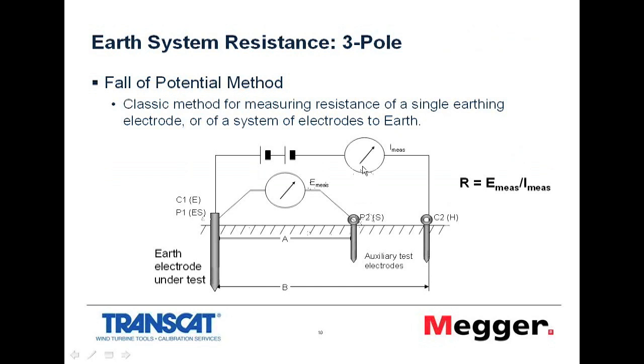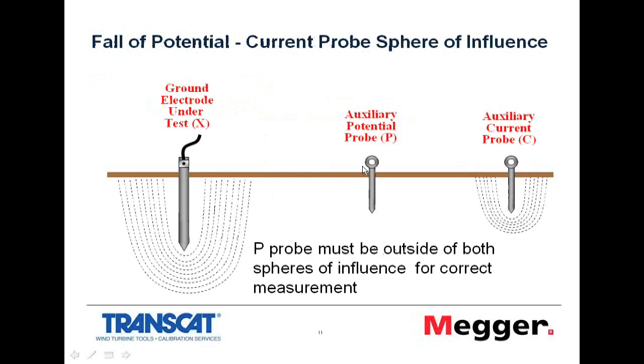Okay. However, we also have to take into account that the ground electrode under test has what we call a sphere of influence. In addition to that, so does our current probe we've placed in the ground. There is also a sphere of influence. And in this, when we're doing this test, we have to make sure the potential probe is not within either of these spheres of influence.